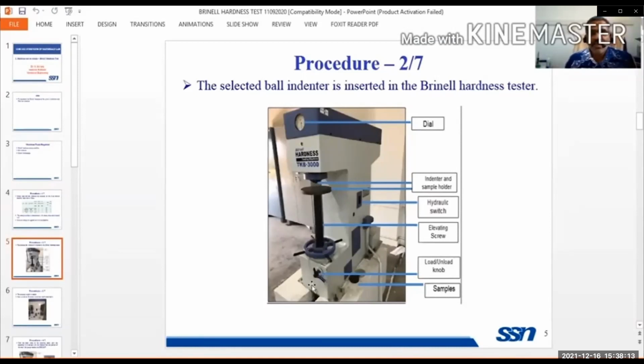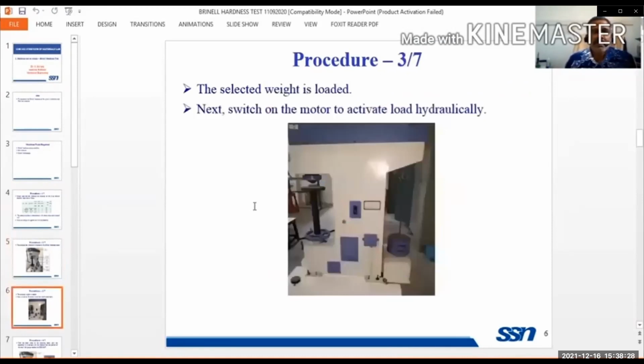Again, here we have the loading and unloading knob. When you rotate it in the clockwise direction, the load is applied on the workpiece by the indenter, and if you unload it, it will be removed. Next, you have to select the weight. I already told you how much weight is to be applied. This is the place where you apply the load. For aluminum you apply 1000 kg, and for steel you apply 3000 kg. After that, you press this button, and the load will be applied. It is a hydraulic system.